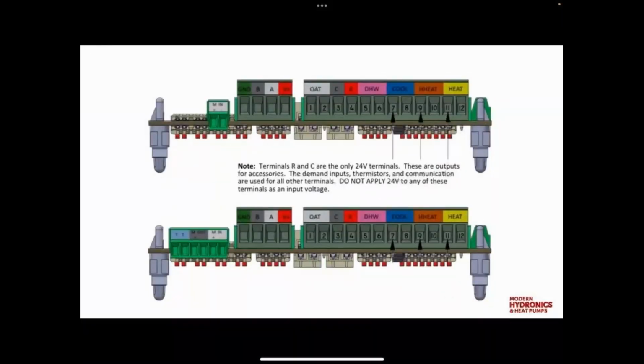As we get into some of the functionality of this equipment, I showed a little bit about the boiler ports on the backside of the heat pump. These are the two different field wiring connection boards, and I wanted to highlight this for a handful of reasons. These two units share the same boards essentially from this area all the way over, so all of the ports to the right of the board are exactly the same. If we start from the right-hand side, we have a heat call and then a high heat call. This is true on both the dual fuel and on the electric backup unit.